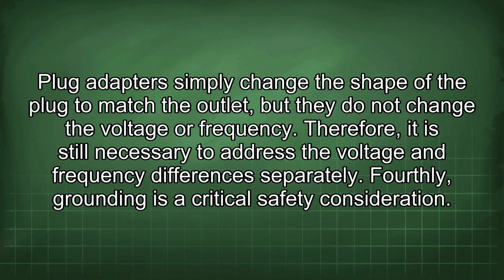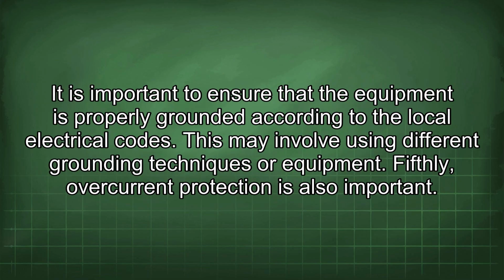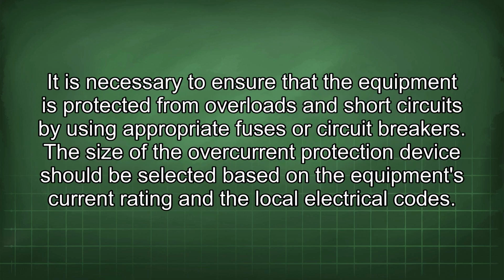Fourthly, grounding is a critical safety consideration. It is important to ensure that the equipment is properly grounded according to the local electrical codes. This may involve using different grounding techniques or equipment. Fifthly, overcurrent protection is also important. It is necessary to ensure that the equipment is protected from overloads and short circuits by using appropriate fuses or circuit breakers.